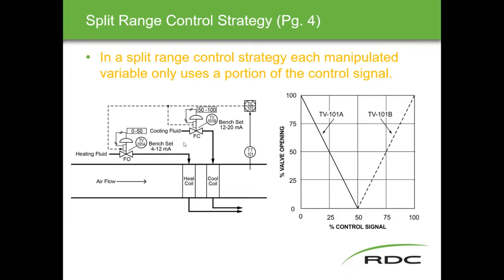It's like a building heat-type arrangement. The heating fluid valve operates from 4 to 12 milliamps (0–50%) and the cooling medium valve operates from 12 to 20 milliamps (50–100%), doing opposite things. The 4–20 mA range is split, and each valve only uses a portion of it.